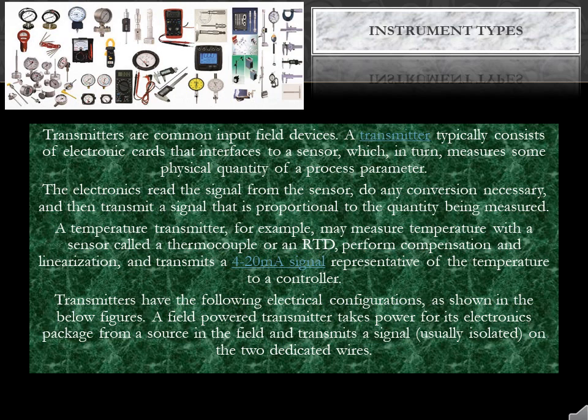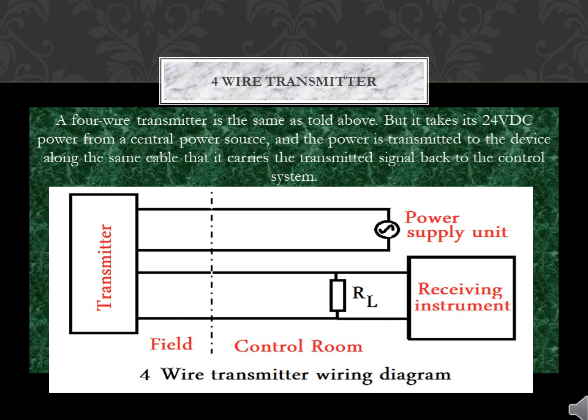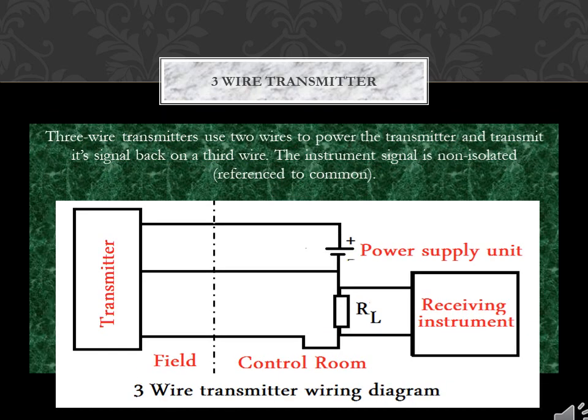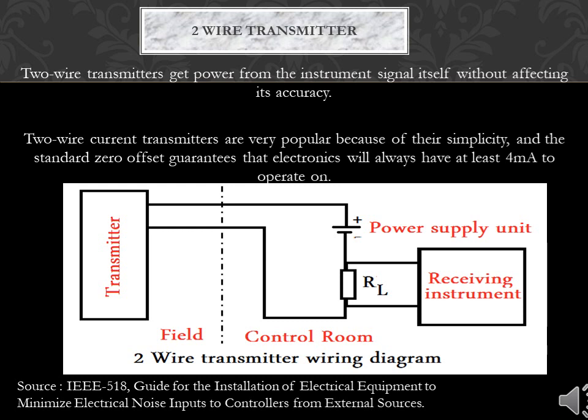Transmitters have the following electrical configurations. A field-powered transmitter takes power for its electronics package from a source in the field and transmits a signal, usually isolated, on two dedicated wires. A 4-wire transmitter takes its 24 VDC power from a central power source, and power is transmitted to the device along the same cable that carries the transmitted signal back to the control system. A 3-wire transmitter uses two wires to power the transmitter and transmits its signal back on a third wire; the instrument signal is non-isolated, referenced to common. A 2-wire transmitter gets power from the instrument signal itself without affecting accuracy. 2-wire current transmitters are popular because of their simplicity, and the standard zero-offset guarantees the electronics always have at least 4 mA to operate on.